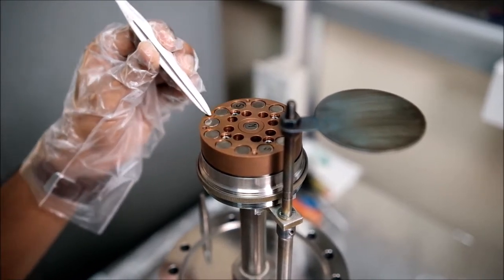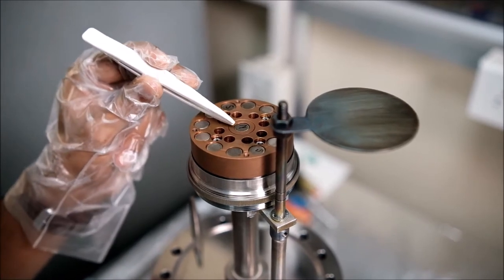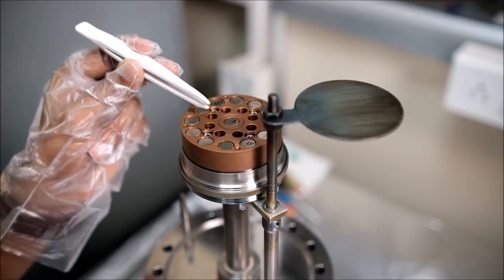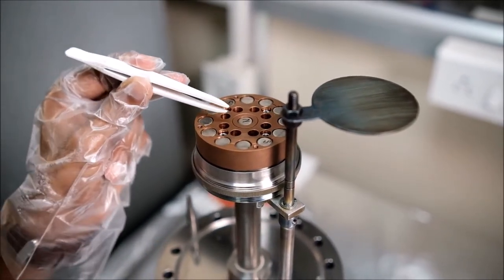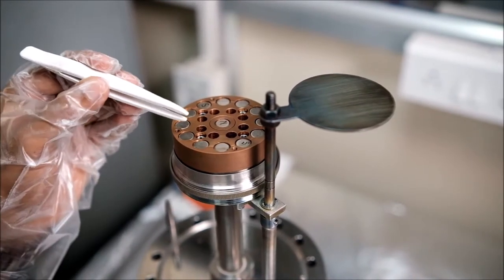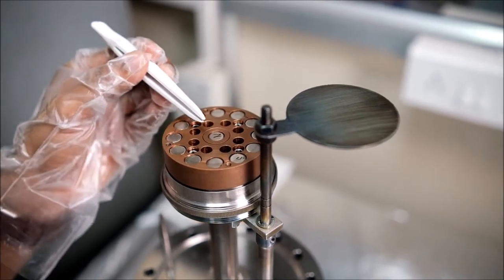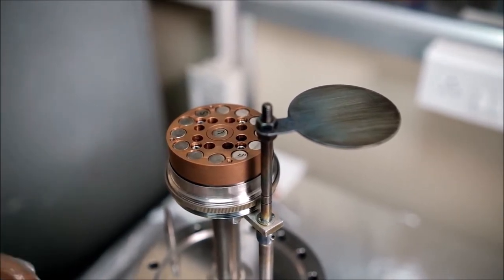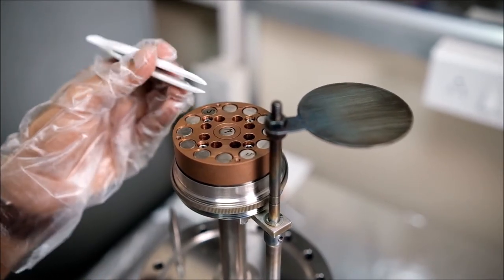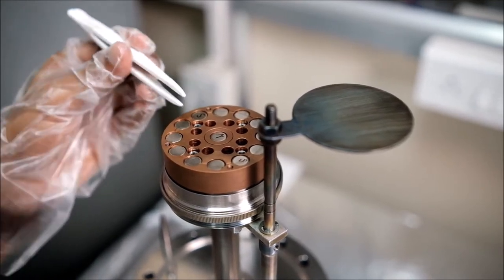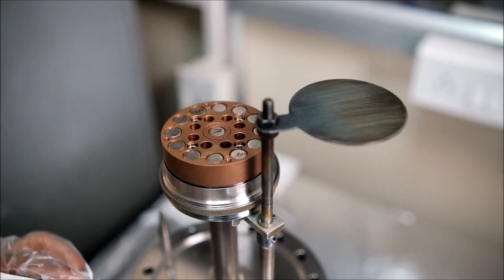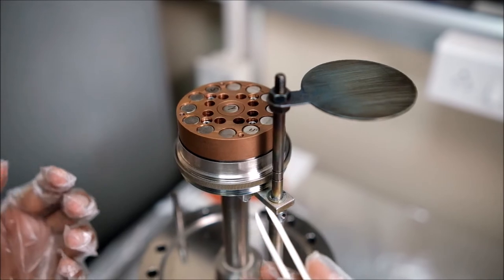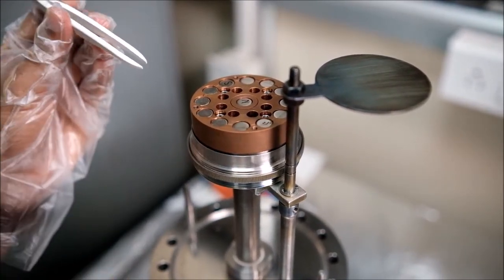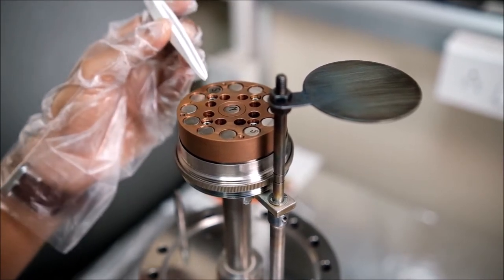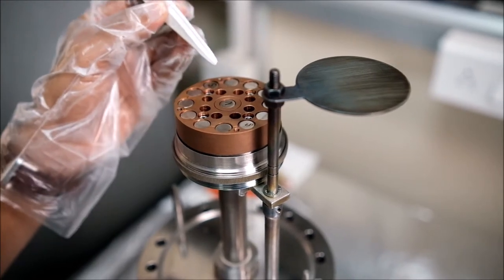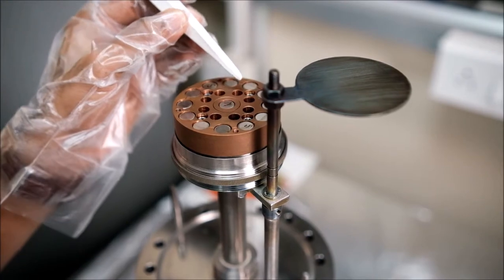Now here, this is the outer ring magnets, and this is the core, another magnet. The core and the outer ring are oppositely faced. So if the outer magnets are south pole faced, then the inner core will be north pole faced. Thus, a magnetic field is created, which lines from this to this, north to south pole. This magnetic field traps the electrons, and also because of this magnetic field direction, the electron path becomes elliptical. So in this way, the electrons' mean free path gets increased, and more ionization happens from argon to argon plus. And because these electrons are mostly surrounding this part and get most of the energy in this path, most of the argons get ionized in this area only, and most of the sputtering also happens in this part only.